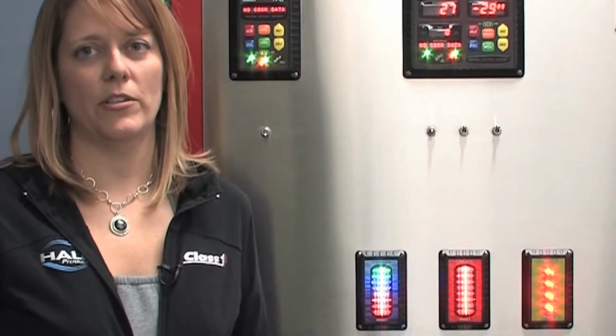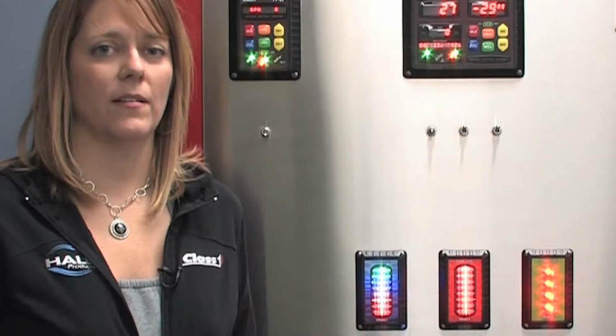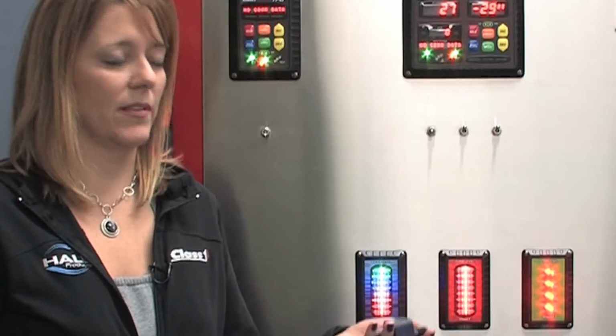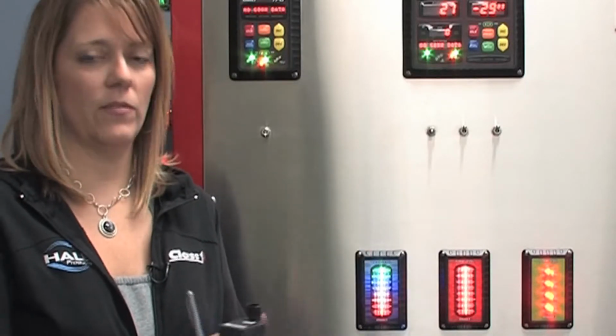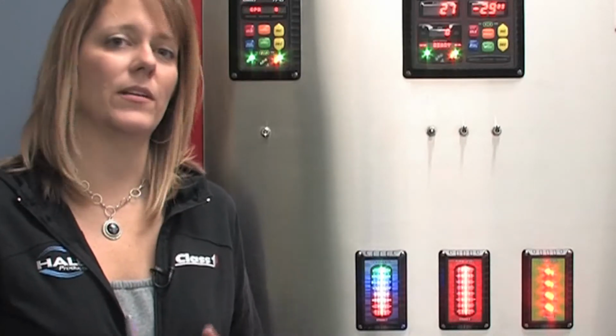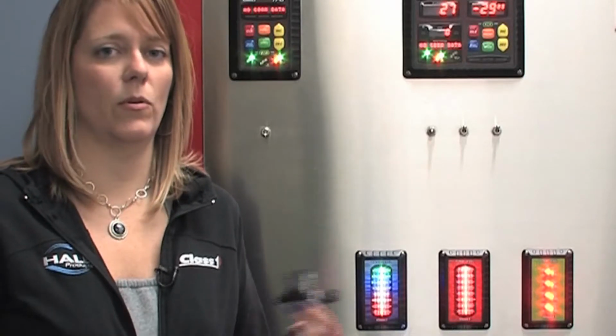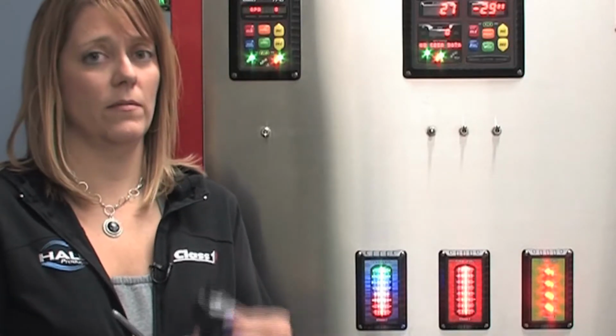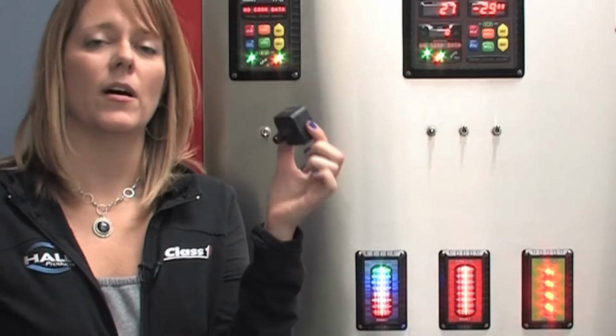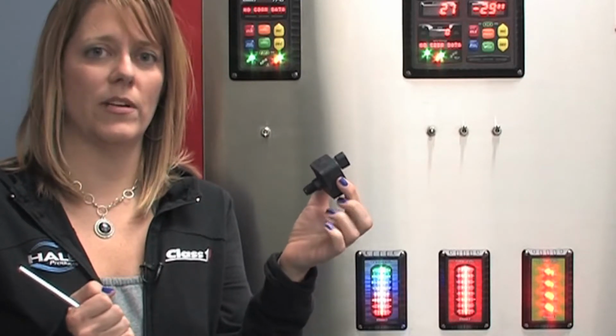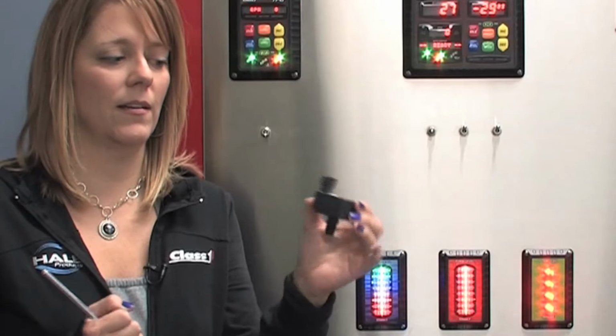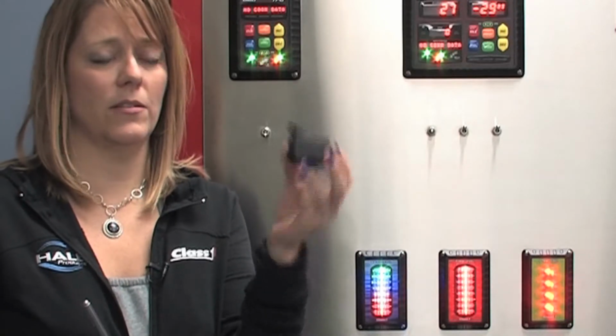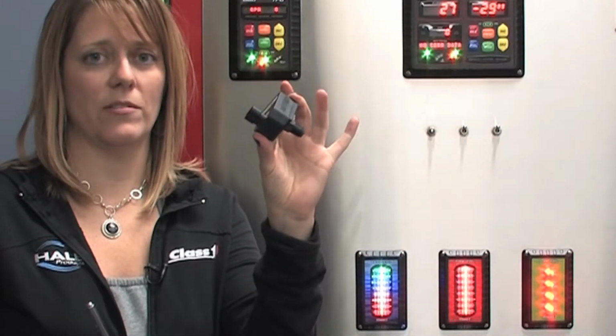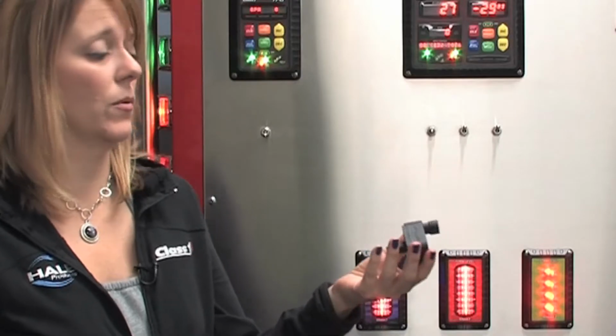For a 2-point calibration, when you want to start with a full tank, we have a different calibration sequence than the last one. And I also have a little trick for you. If your water tank is already full, you can either empty your water tank into a fold-a-tank type thing, or if you have a second pressure transducer, unplug the harness from the pressure transducer that's already located in your tank and plug the harness into your second backup pressure transducer. This will actually simulate an empty tank situation, so it saves you from actually having to empty your water tank.